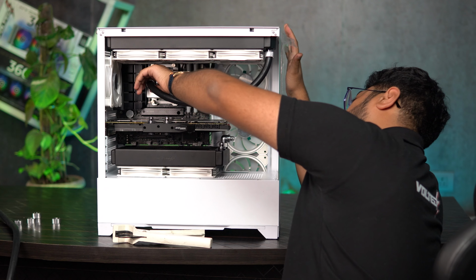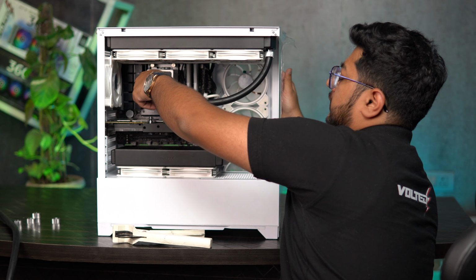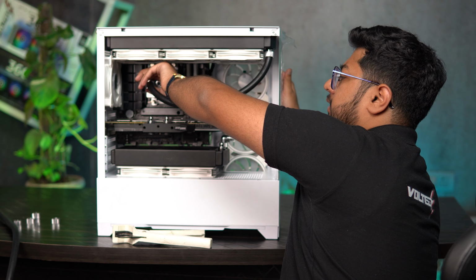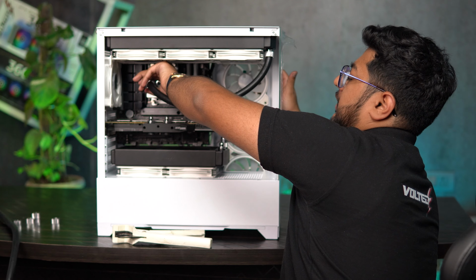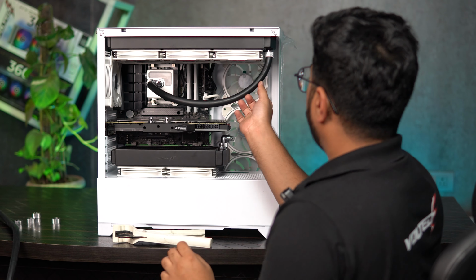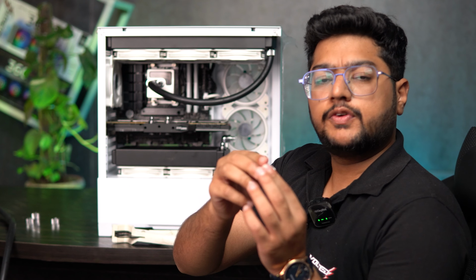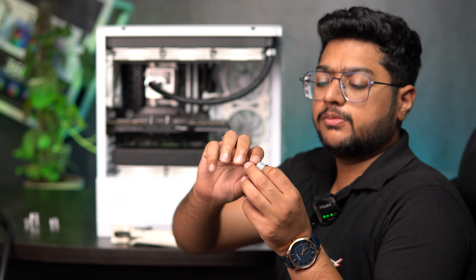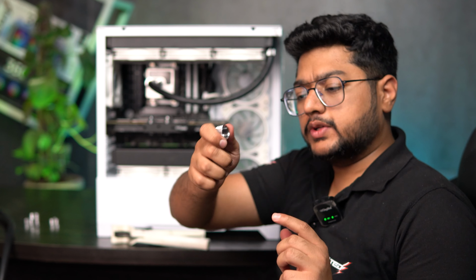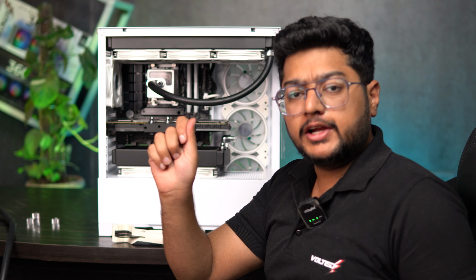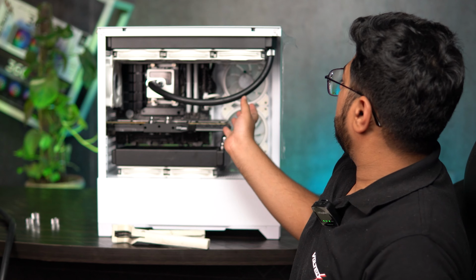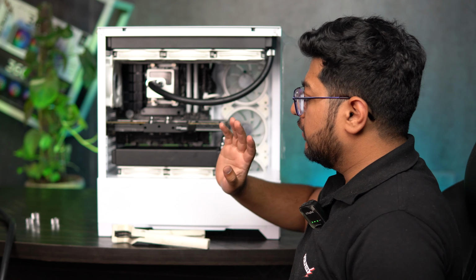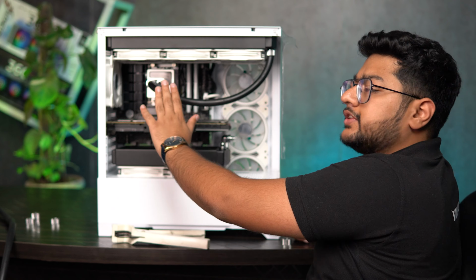In liquid cooling, make sure you hand tighten all the products and don't use a plier to do it. The reason is all the components are very fragile, and a hand tight fit is good enough. These fittings have a textured surface to help create friction to twist and rotate them, but it will definitely take a toll on your fingers and thumb because they are quite hard to turn. Even if you want to use a plier, use a silicone plier or a thick cloth between the plier and the fitting. Now our first connection is done, we have successfully connected the water block to the radiator.